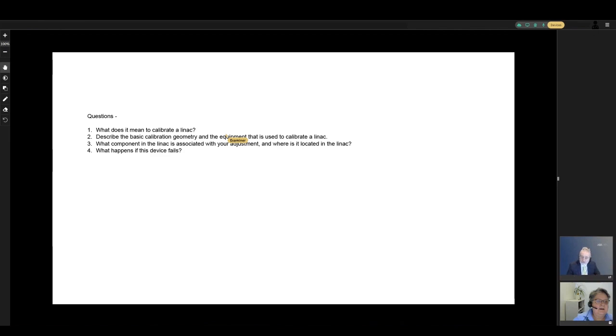Okay, is that the only way that you can calibrate a Linac, that is with 100 centimeter SSD? Yeah, so the first part of measuring the PDD, that needs to be done at 100 SSD. That's what TG51 recommends. The second part where you actually calibrate your machine, so you select a point where you measure a centigray and relate this to the monitor unit, that can be an SSD or SAD setup.